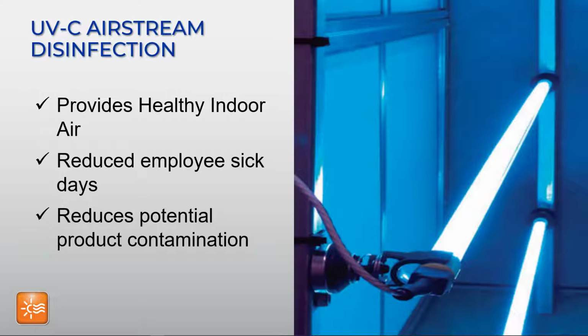This requires more energy to kill the bugs while in the air versus simply surface cleaning. The mixed air units are a perfect fit for this kind of system. As the air passes over the UV bulbs multiple times, more and more microorganisms are removed. This will continually clean the air as it moves through the space.